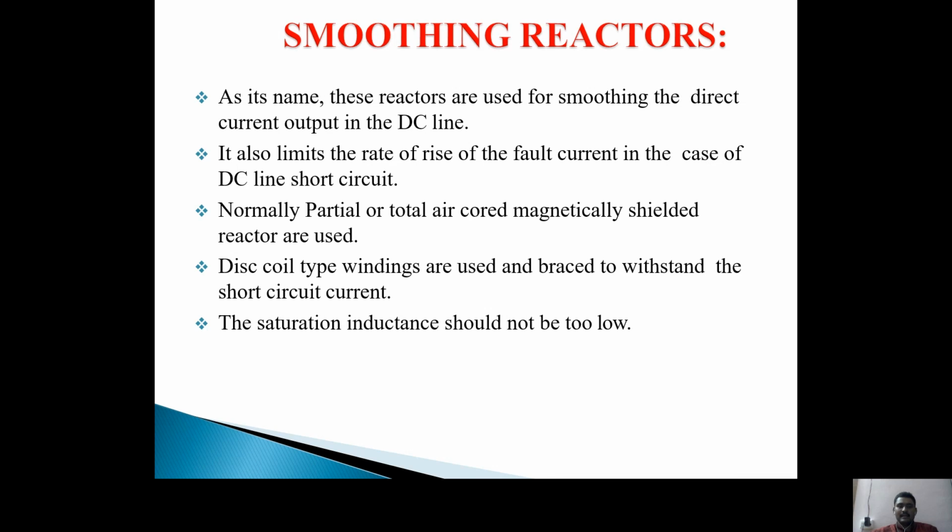Normally partial or total air core, magnetically shielded reactors are used. Disc coiled windings are used and braced to withstand the short circuit current. The saturation inductance should not be too low.